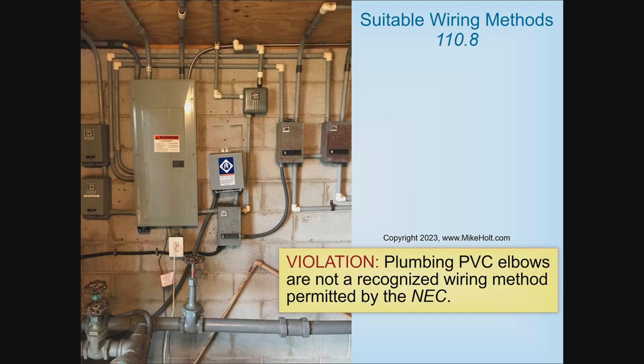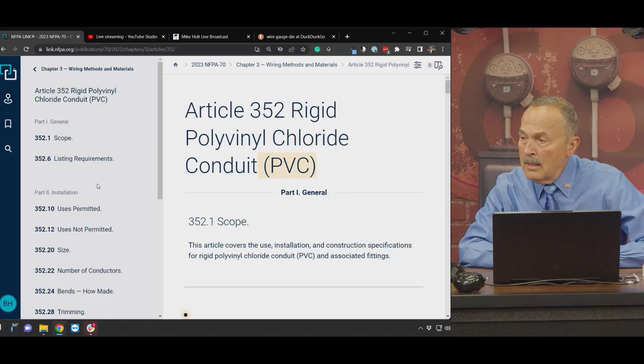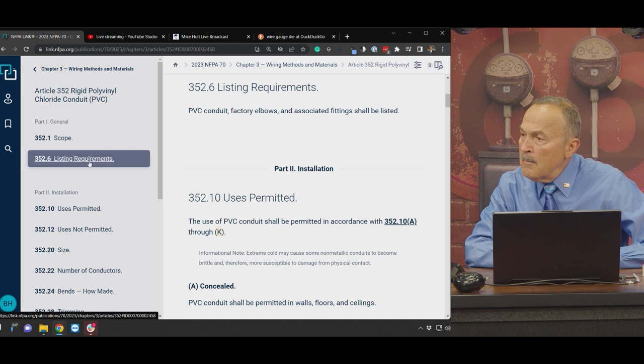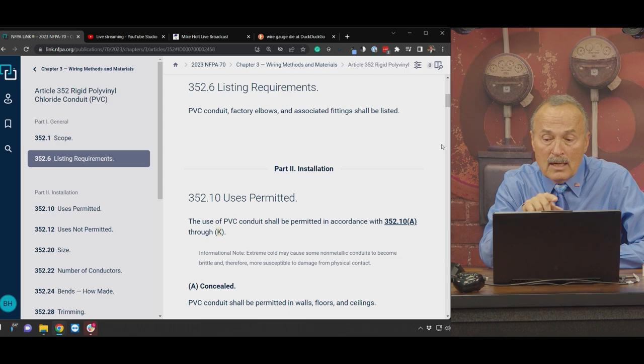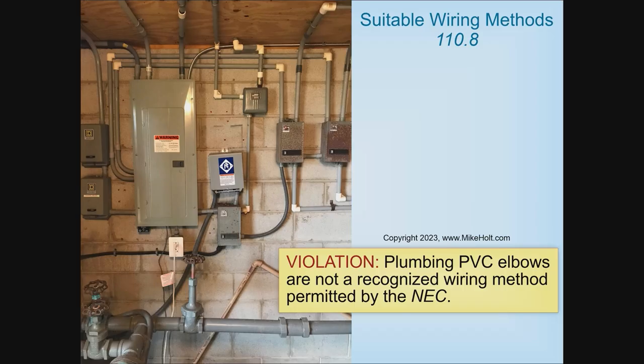Let's go to the wiring method contained in the code for PVC — Article 352. Let's look at 352.6, which talks about PVC conduit, factory elbows, and associated fittings shall be listed. We can make this a 110.8 code violation, and we would also say that it violates 352.6 — these fittings are not listed for that particular application. And one more violation: 300.15. What is 300.15? Fittings must be designed for the specific raceway. We could also use 110.12 and say that's a sorry job for execution at work — it's not professional or skillful.